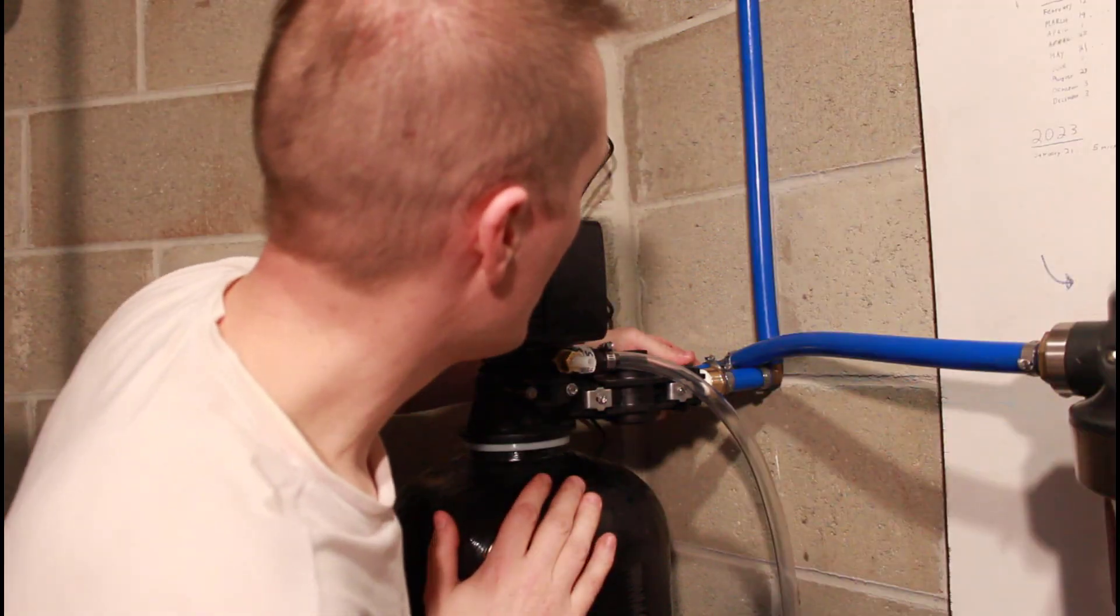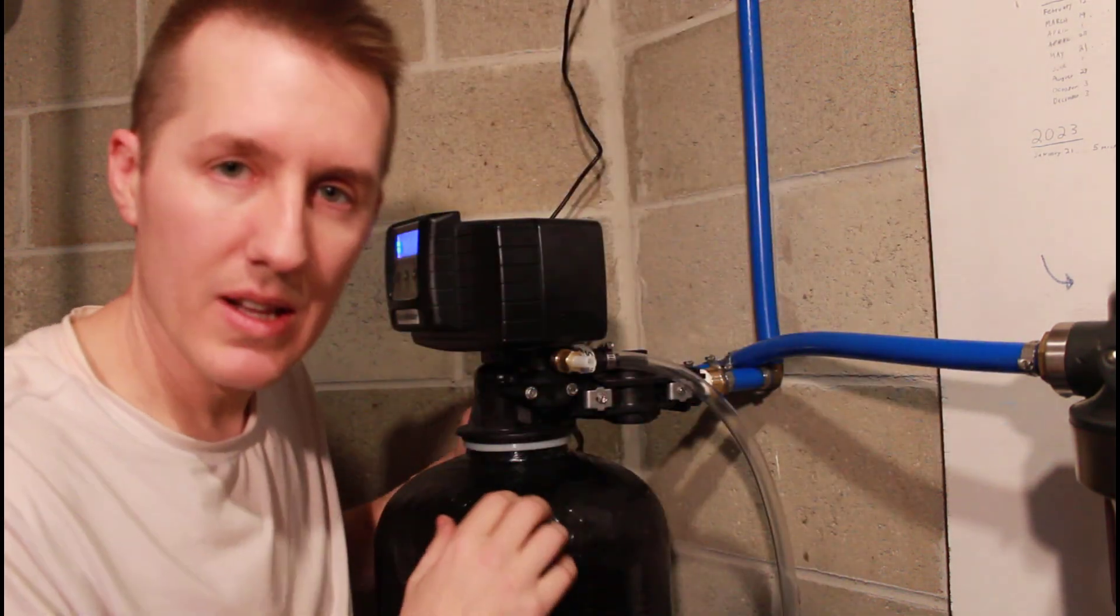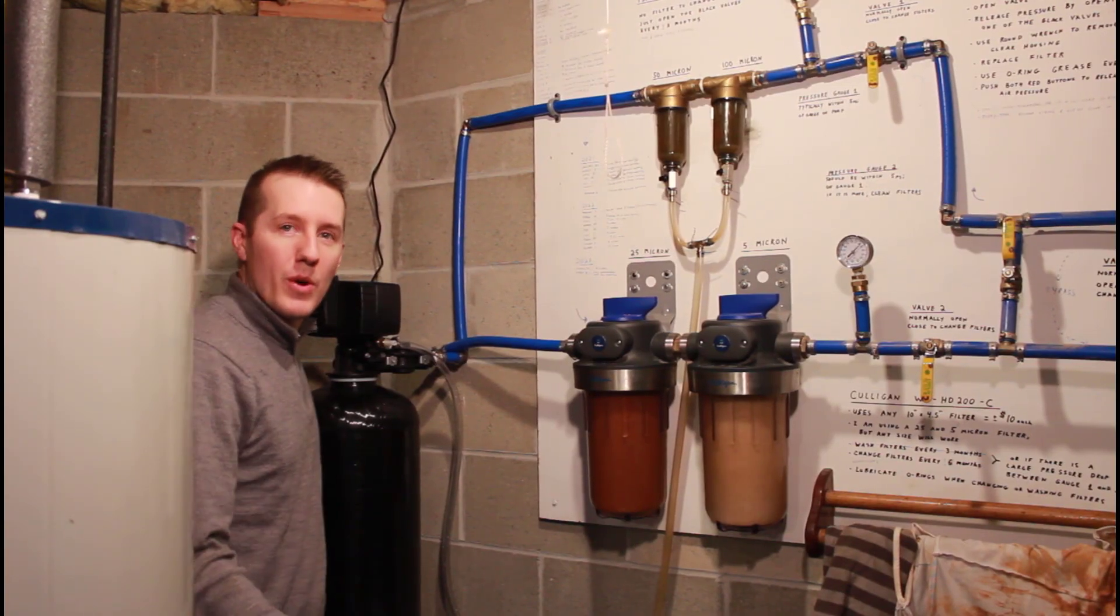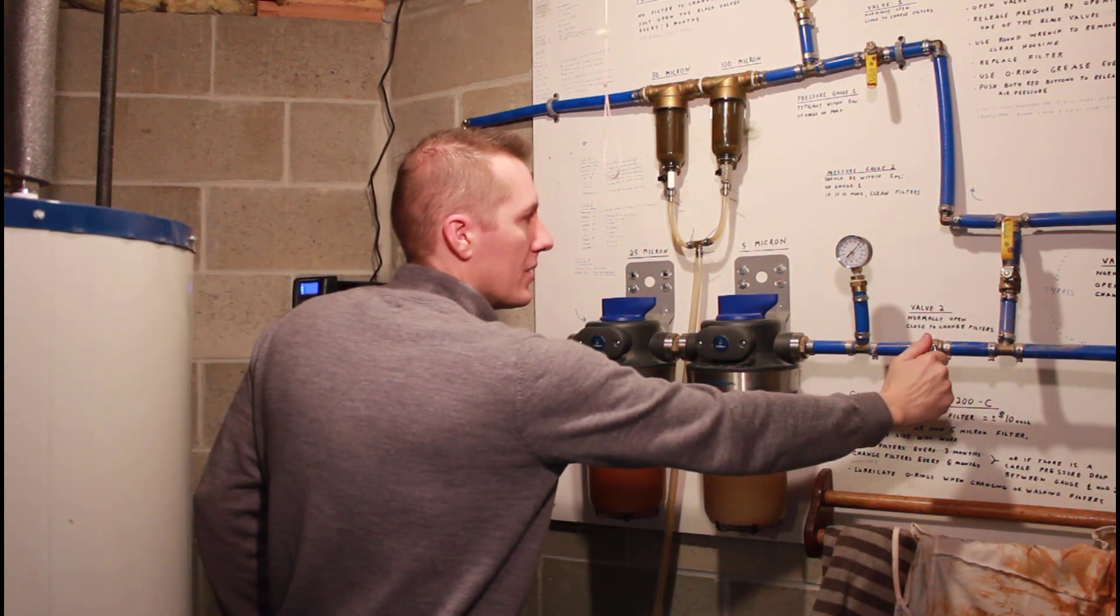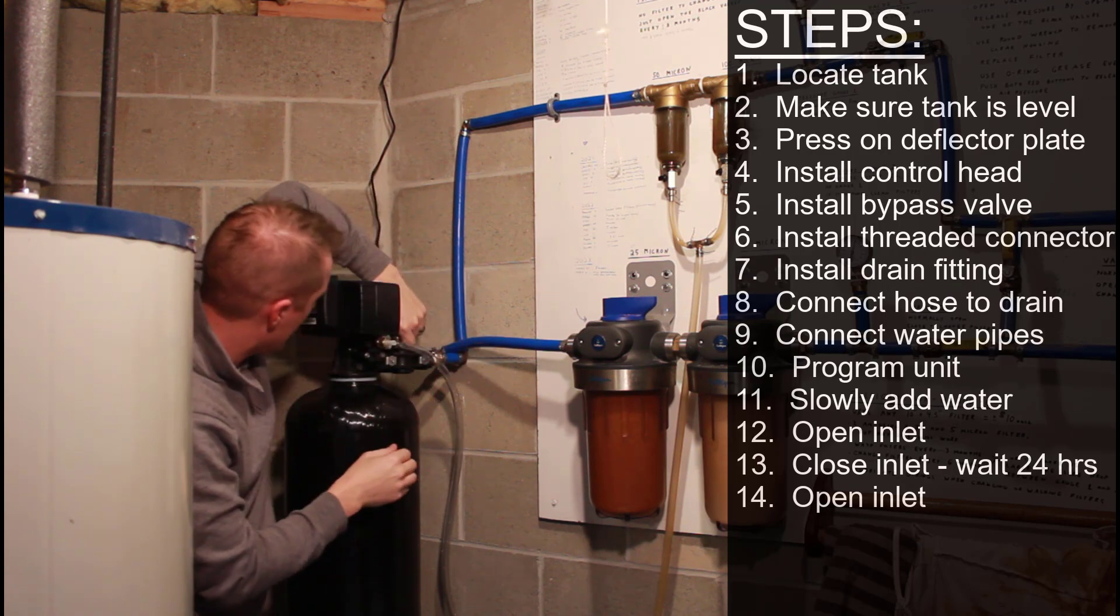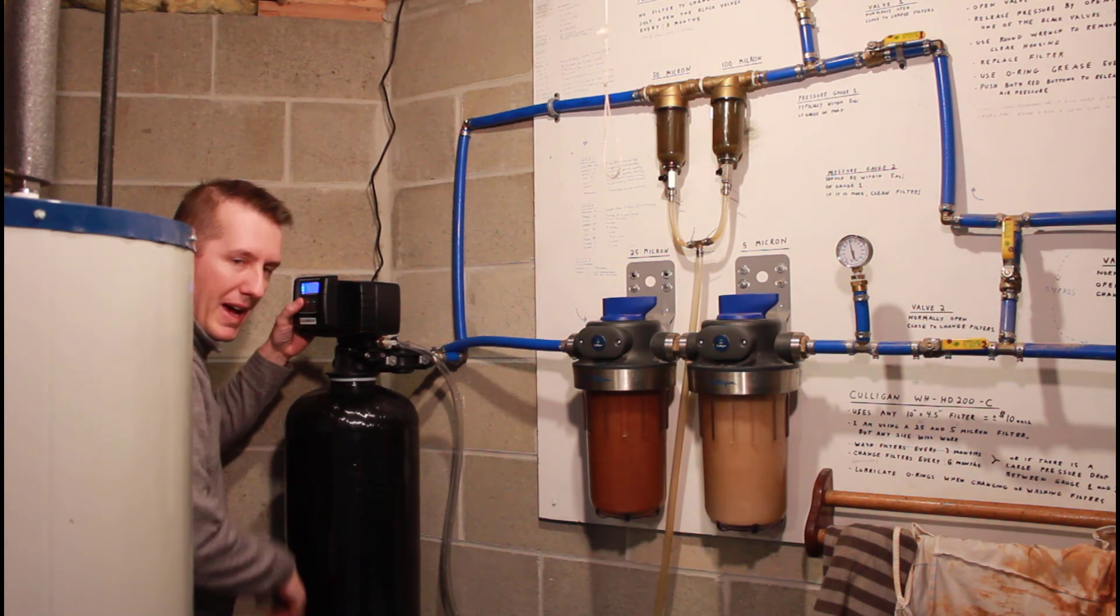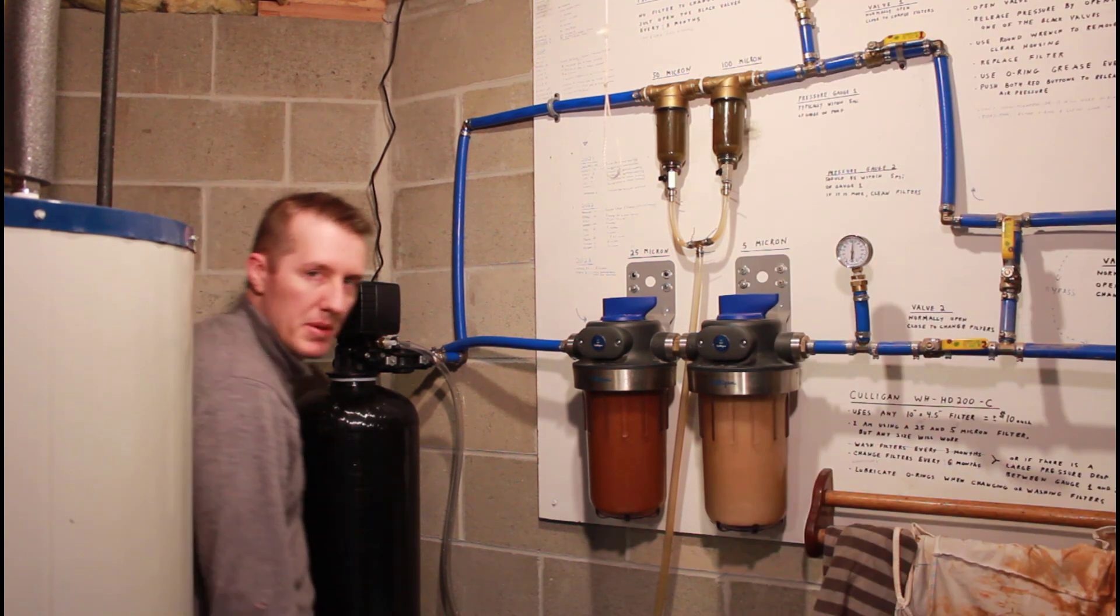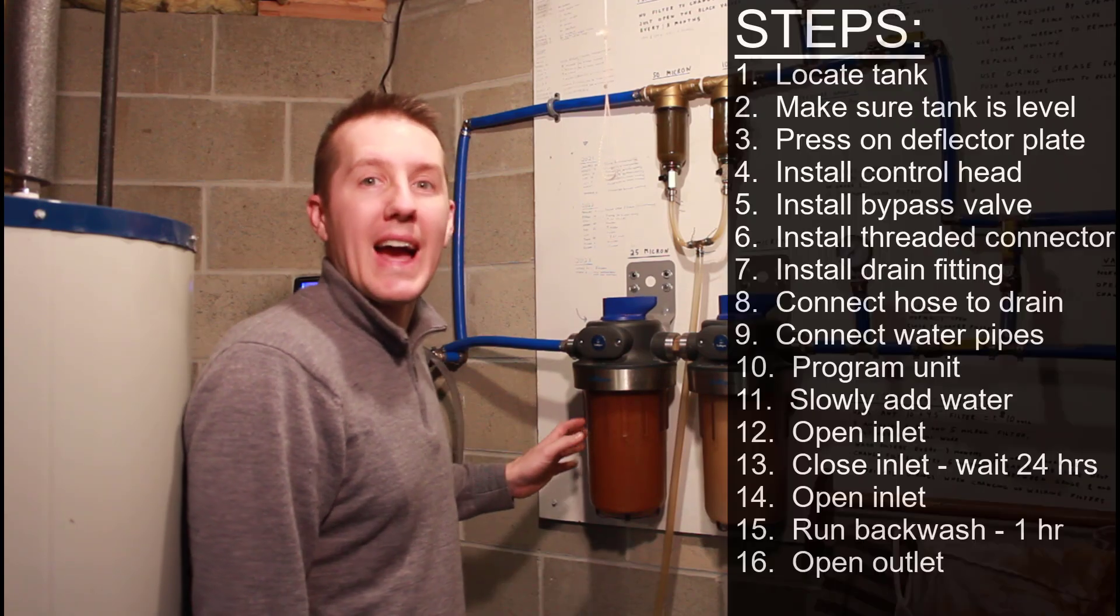Okay, it's been 24 hours. Hopefully all that media is settled down in there. I'm going to turn on the water slowly. And then it says, open the inlet. Then it says, press and hold the far left button to do a backwash and let it run for one hour. It says BW, so backwash is running. After one hour of doing the backwash, I'm going to open the outlet. I can see it's already draining water out here.